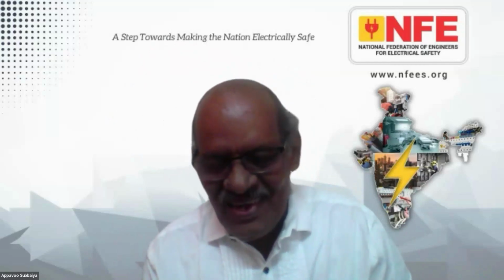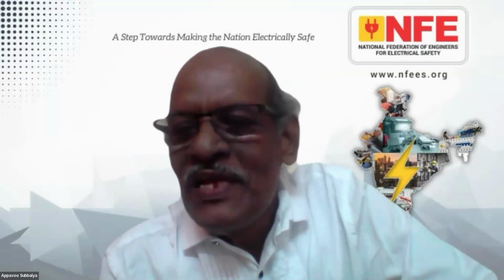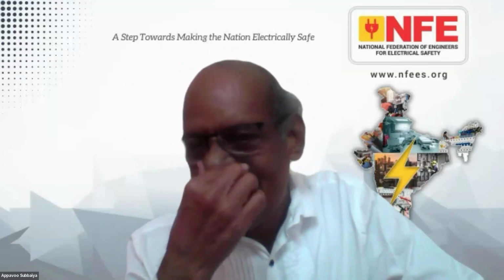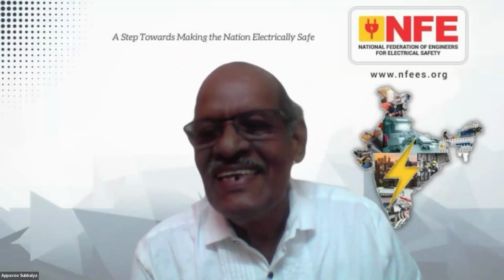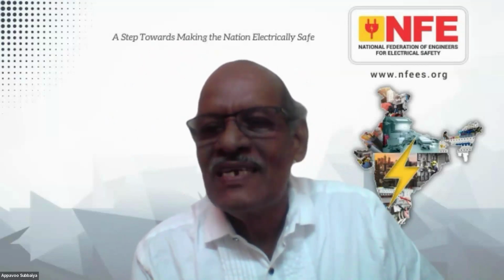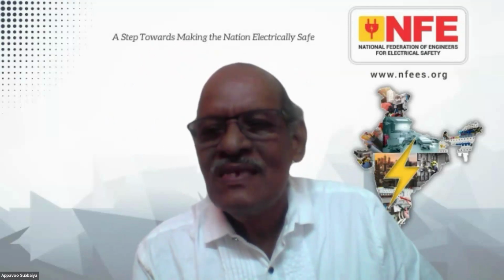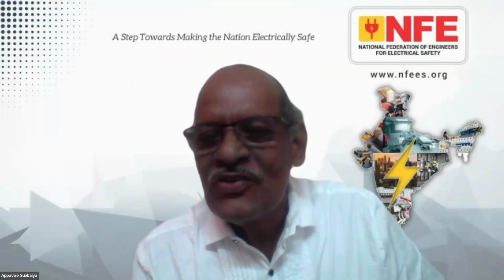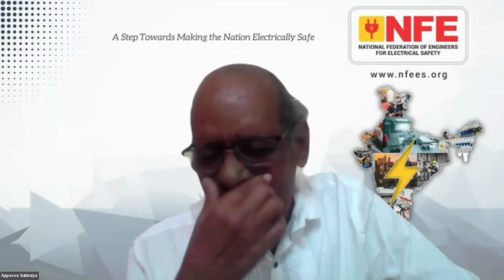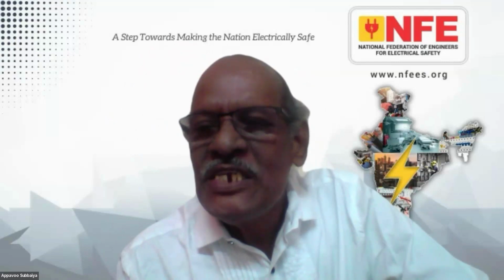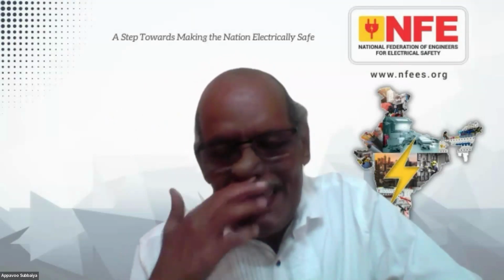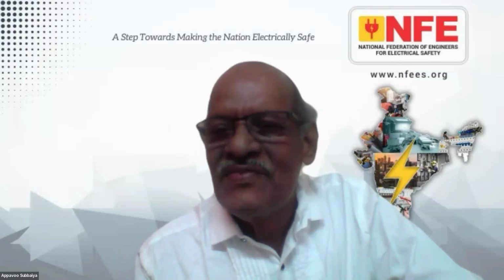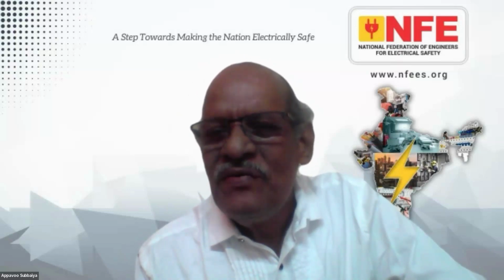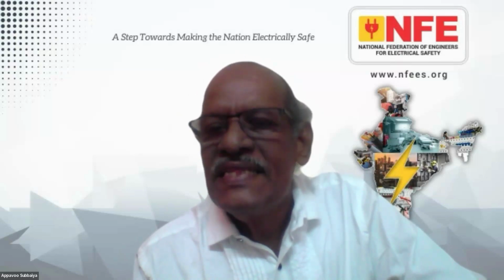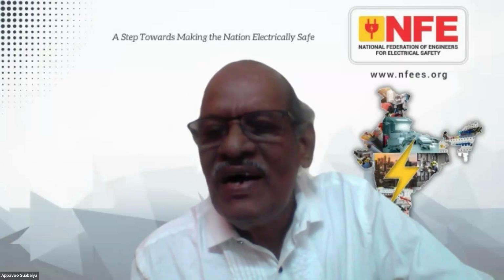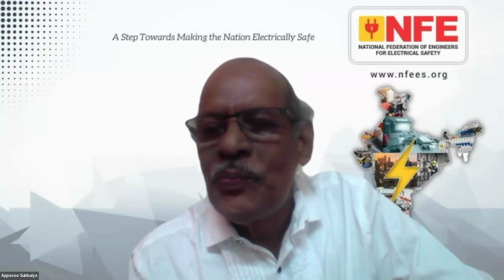This is an area where both the consumer and the suppliers make a lot of errors, a lot of non-compliance. If the supplier complies with regulation 18 regarding the PME system interconnection everywhere, then you will be at liberty to connect your earth terminal. If it is missing, then you will be at stake and forced to disconnect. But by not connecting your earth terminal with the supplier's neutral, you subject your equipment to risk. Nowadays we have costly and fragile power electronic devices - LED, TV, or inverter AC - everything is susceptible to temporary over voltage which they can't withstand. You can temporarily avoid shock, but your equipment will be subjected to damage.